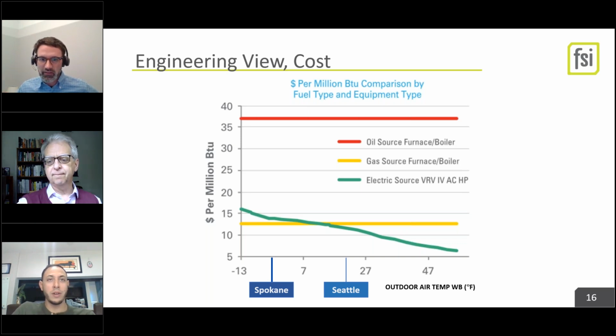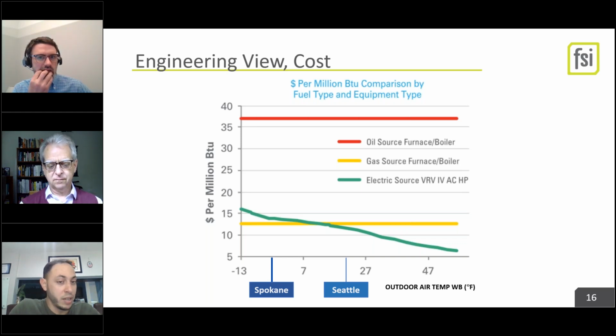Next slide. There's a question, very relevant to electric resistance: can we still use electric resistance heat to preheat the outside air for water source heat pumps, where ERVs are not required, to keep the water source heat pumps at a high enough inlet air temperature to prevent head pressure trips? That is extraordinarily expensive.